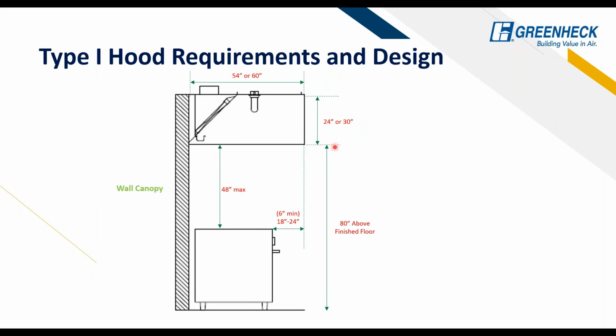As well as this, 80 inches above finished floor from the bottom of the hood to the ground. We need that 80 inches above finished floor. You cannot go lower than that. You are able to go higher than that if you keep this 48 inch max, but you cannot go lower than 80 inches. And then, we can go anywhere from 48 inches deep all the way up to 72 inches in 3-inch increments, depending on what appliances we're looking at.